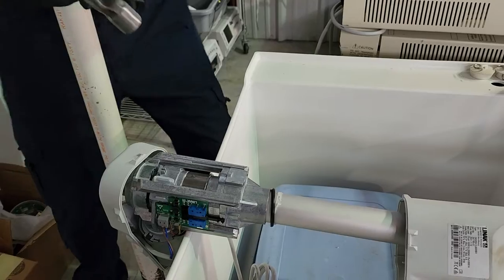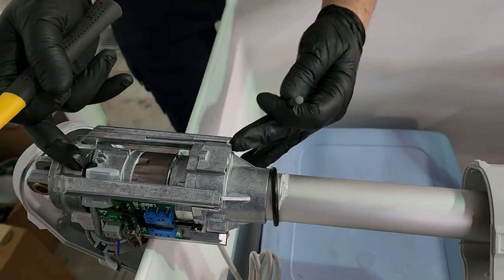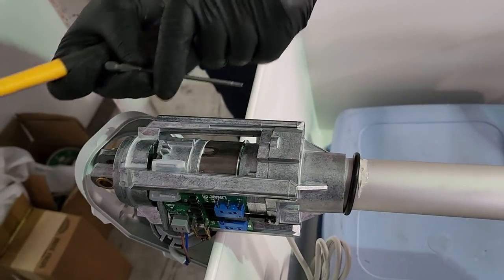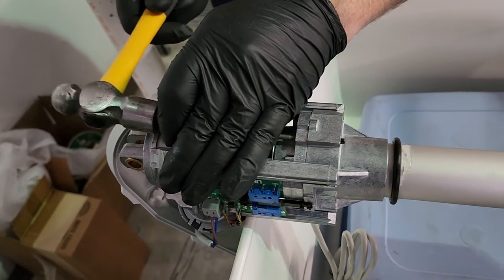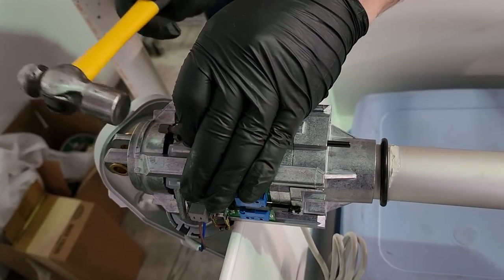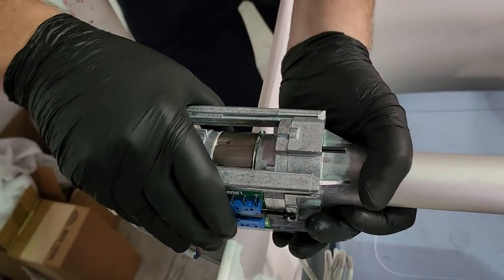The way that we do it — take a pin driver. On this face there is a roll pin. Not only is there a spider that holds the front of this — it's a metal plate with four bolts — but then there's a tiny little roll pin that we drive out. Look at that — I'm going to leave it right there.